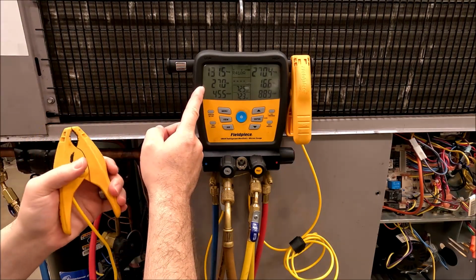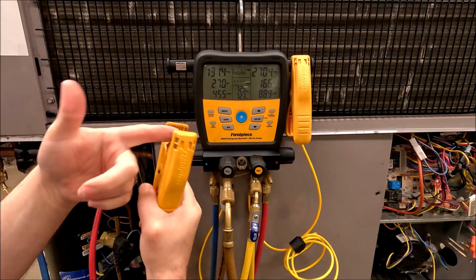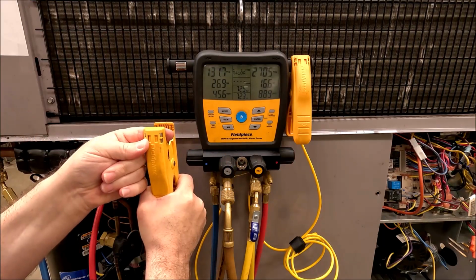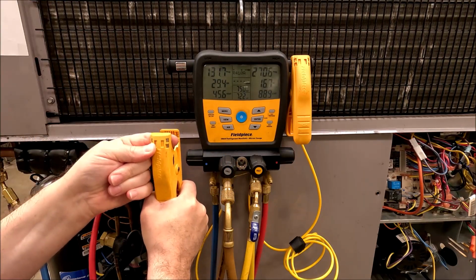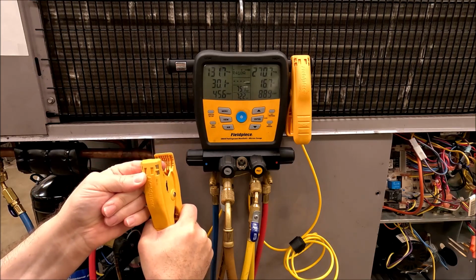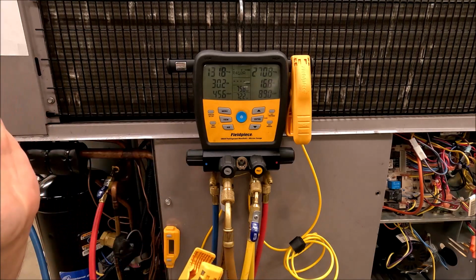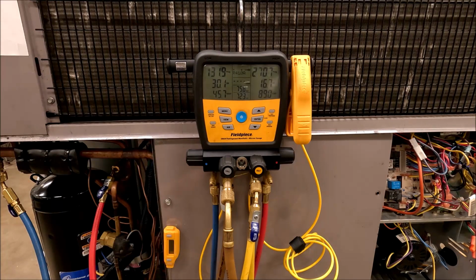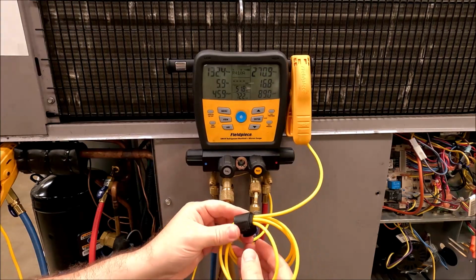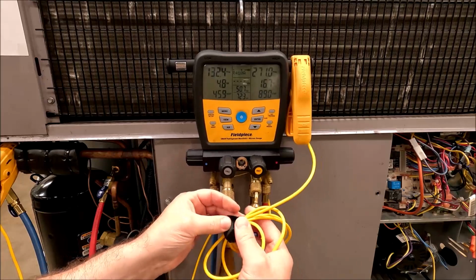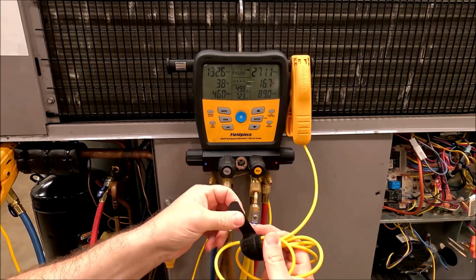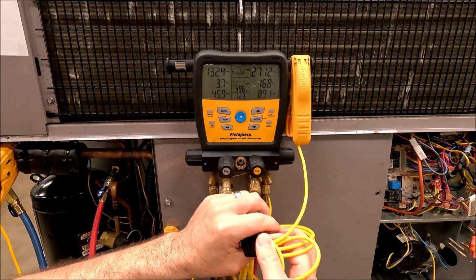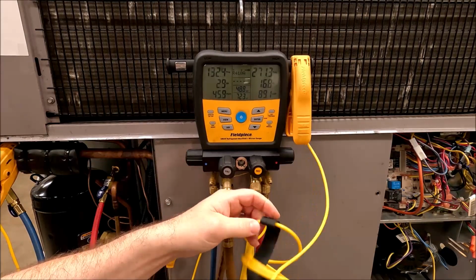And you can see here it's already reading superheat, and I haven't even touched anything. If I put it on my hand, you're going to see the superheat change. Oh, 30, 40, you know, whatever it's going to be. Okay. We have to put it on the vapor line. So I'm going to clamp it right next to what happens to be the access port on my vapor line. I've got another pipe clamp, and this one's going to be dedicated for the hot side. So we're going to be doing subcooling with it. So I'm going to unloose all this cabling.